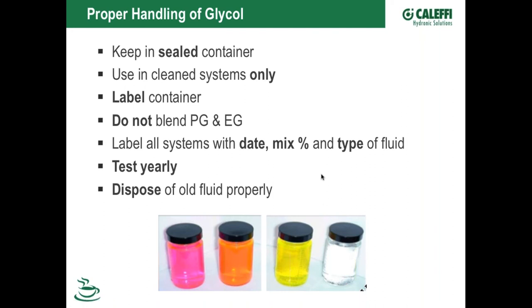When glycol is put in, it'll have a sweet, almost sugary smell. When it breaks down, it gets a smell people describe as a cross between a men's locker room and cotton candy. It's still got a bit of sweetness, but also a musty, old, stinky smell. Put your meter in it, but that smell is an indication that the glycol has been destroyed, and it's time to clean it and flush it out.